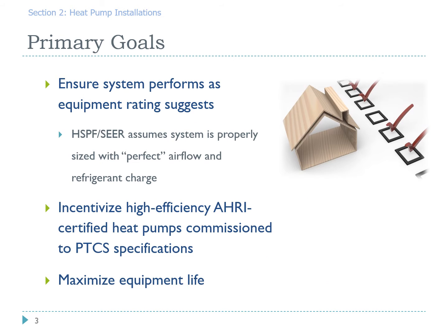The primary goals are to ensure the system performs as the equipment ratings suggest. Those ratings are HSPF and SEER, and they assume that the system is properly sized, has perfect airflow, and the right refrigerant charge. Another goal is to incentivize high efficiency AHRI rated heat pumps that are commissioned to the PTCS standards, and to maximize equipment life.